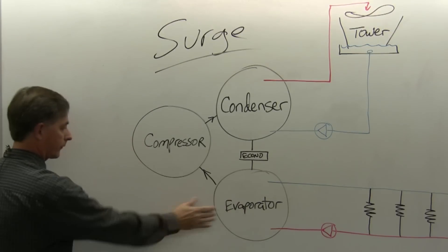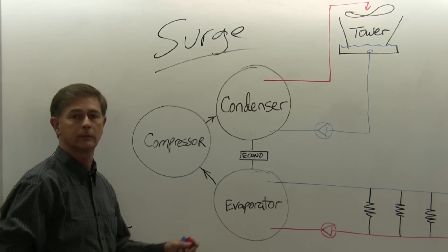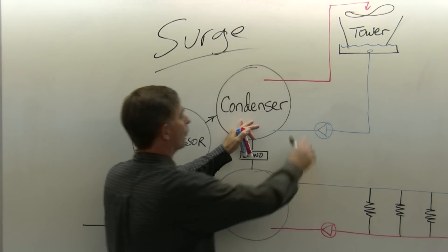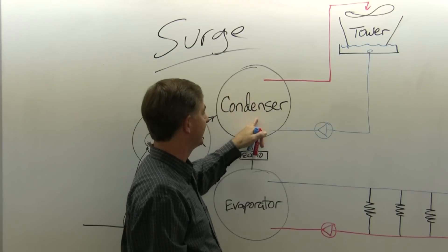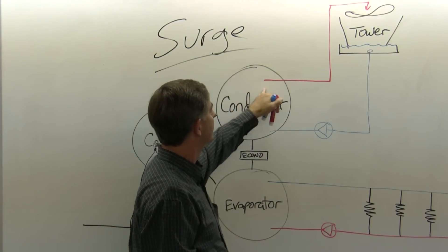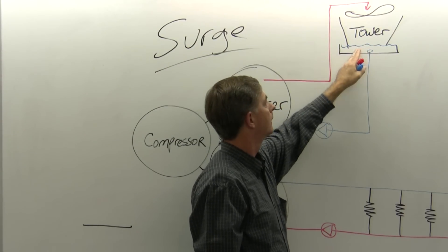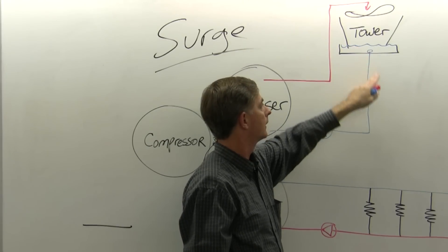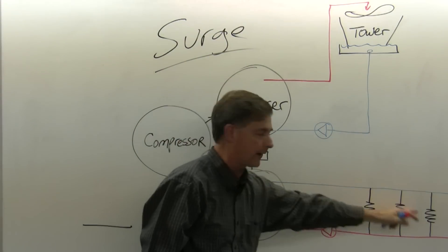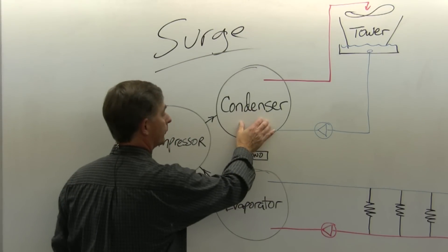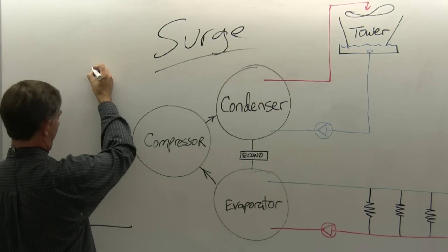This compressor takes this refrigerant at this pressure and it lifts it up to the condenser. This condenser takes water from the tower, heat exchange from the warm refrigerant into the tower water, sends it out to the tower, goes in the tower, flows through the tower fill, cools through evaporation, and returns through your pump back to the condenser. The temperature and pressure of this vessel, I'm going to represent with a mark, that pressure is right there.